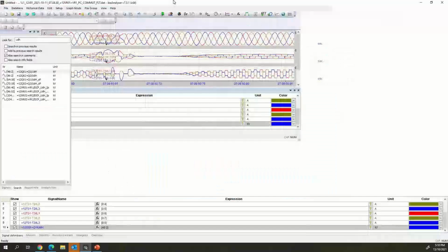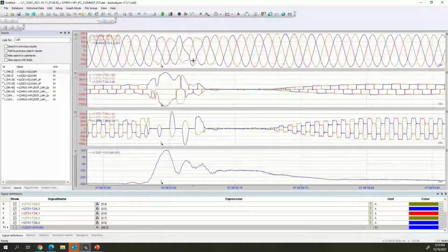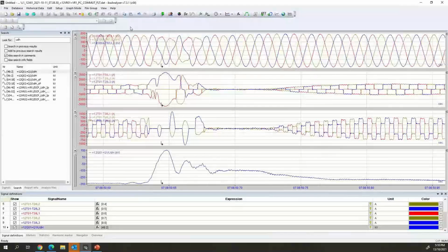I thought I might get asked this question, so here's a commutation failure. You can see this is the AC voltage up the top here. This is at Haywards. This is one 6-pulse bridge current and another 6-pulse bridge current, and this is the DC voltage. So you can see things go wobbly, and the commutation failure actually causes the voltage to be worse than it would have been if you hadn't had the commutation failure. But you can see basically you just block all the firing pulses, wait for all the rubbish to clear out, and then fire up again. We're talking within 100 milliseconds, we're back online again. So generally you've got enough inertia in the 2 grids to be able to withstand an interruption of that duration.